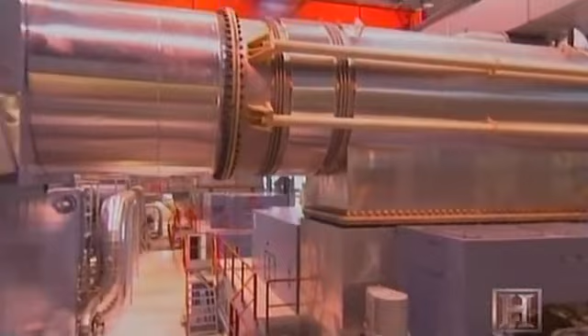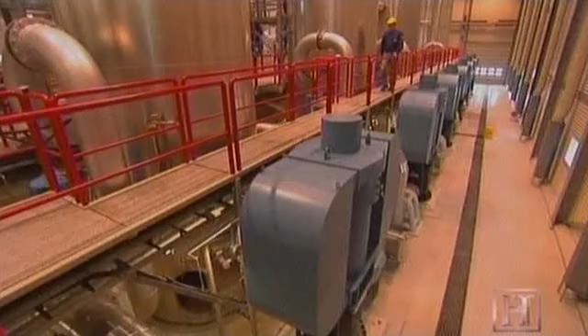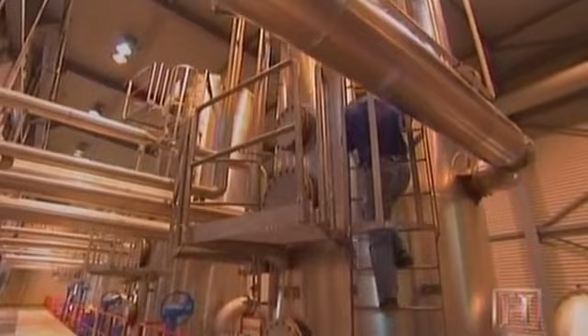125 Fahrenheit is not hot enough for us, so we have to heat the water a little bit more, up to 86 degrees centigrade. It's about 187 Fahrenheit. And we do that in a heat exchanger. Inside the heat exchanger, the geothermal brine rapidly brings the fresh water to its 187-degree target temperature. The now scalding fresh water is pumped into the pipeline as it climbs uphill. And from there, the water flows through the pipeline by gravity to Reykjavik. And the heat loss on the way is less than 2 degrees centigrade, it's 1.8. So you could say that the pipeline is, well, the insulation is almost perfect.